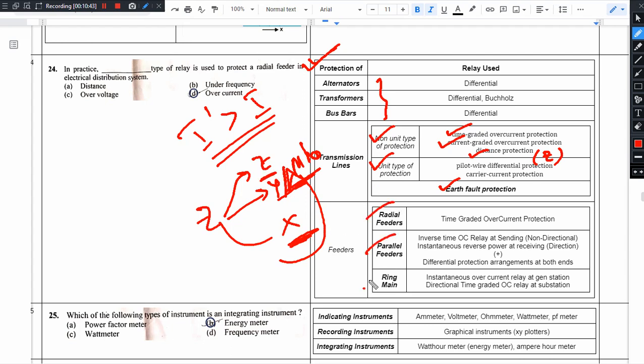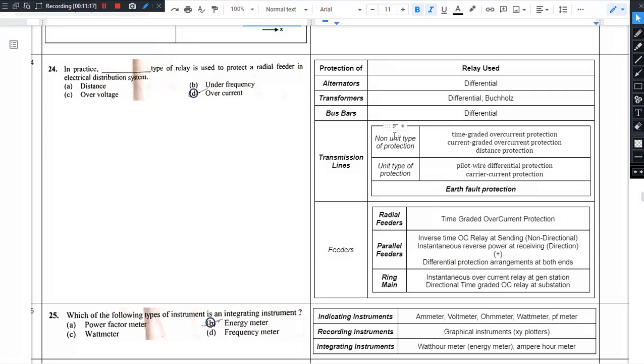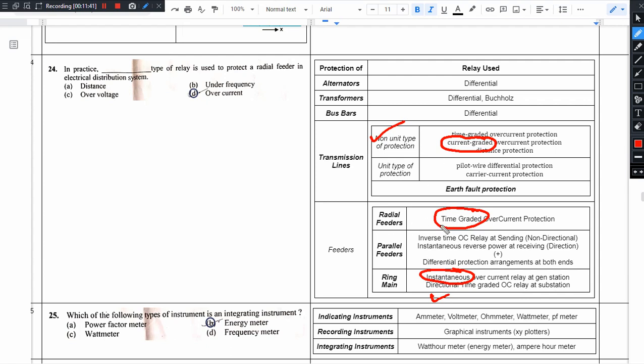Feeders: radial feeder uses time-graded overcurrent protection; parallel feeder uses sending end non-directional and receiving end directional, in conjunction with differential protection scheme. Ring main distribution uses instantaneous overcurrent relay. Differential protection is most important for alternators, transformers, and bus bars. To summarize: transmission line non-unit uses current graded; radial feeders use time graded; ring main feeders use instantaneous overcurrent relay.